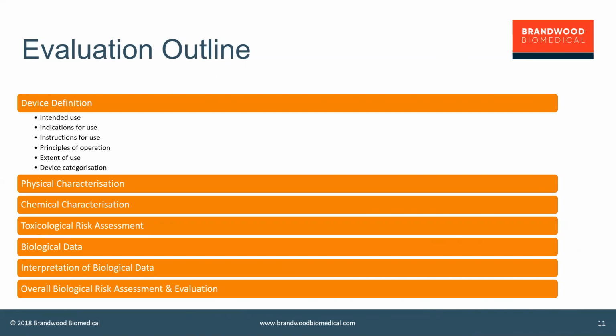Not every evaluation will include biological data, particularly not biological data specifically derived on the subject device. It may rely on biological data that is existing for previous devices or is well known from published literature. So the biological data will of course feature in this, and of course data is meaningless without interpretation, and so there should be an interpretation to follow that data. And then there should be an overall biological risk assessment which takes into consideration all of the above, but specifically the toxicological risk assessment and the interpretation of the biological data.